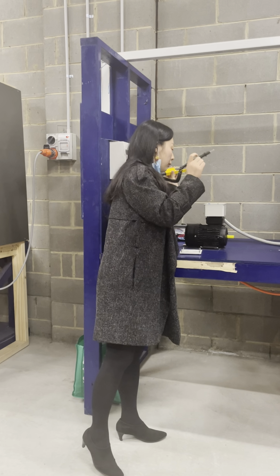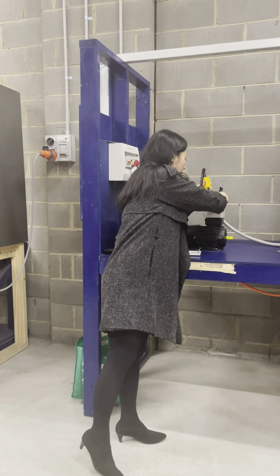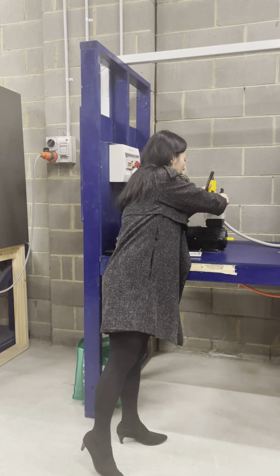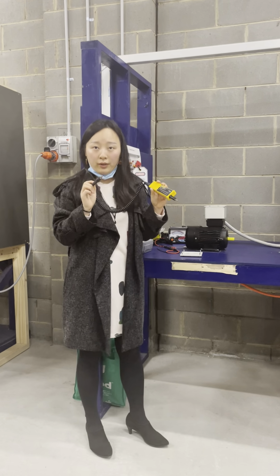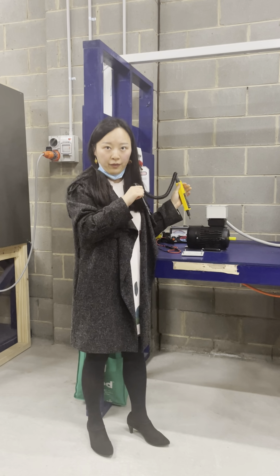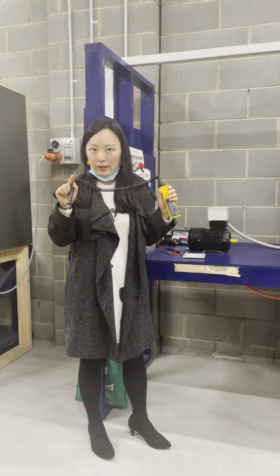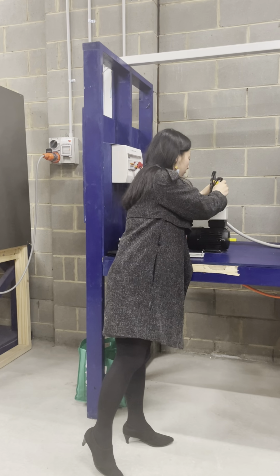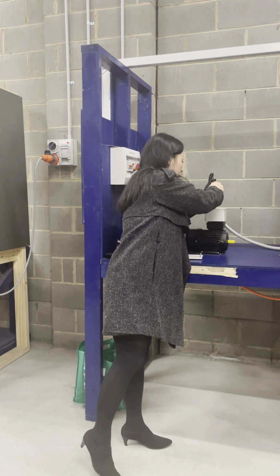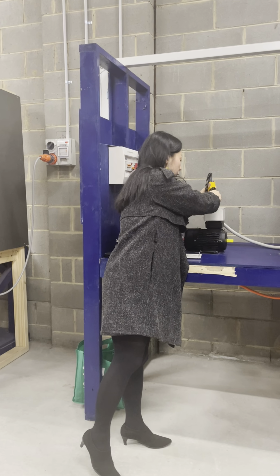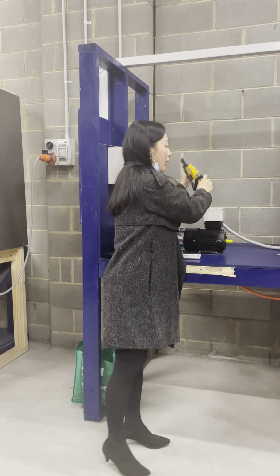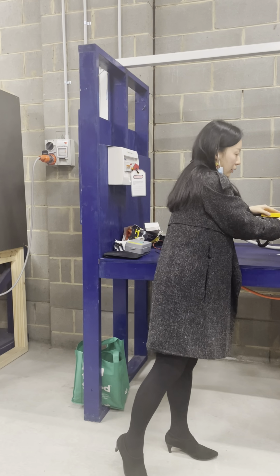Make sure you check between earth to phase 1, phase 2, phase 3. Now this is the most important thing: because this is 3-phase, you need to check between phase to phase as well. So I'm checking phase 1 to phase 2, phase 1 to phase 3, and phase 2 to phase 3. Then retest your tester.